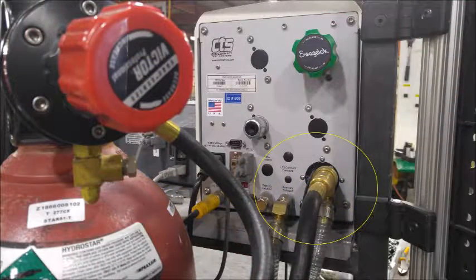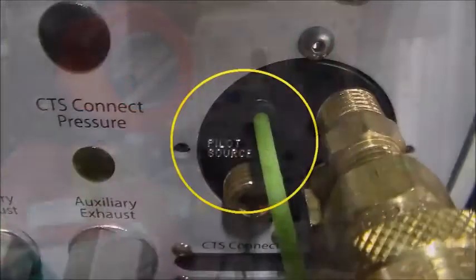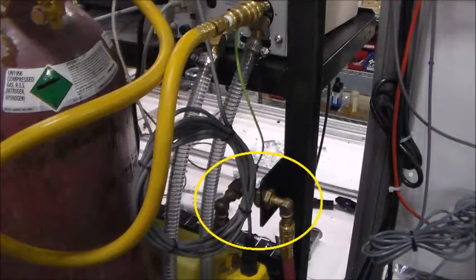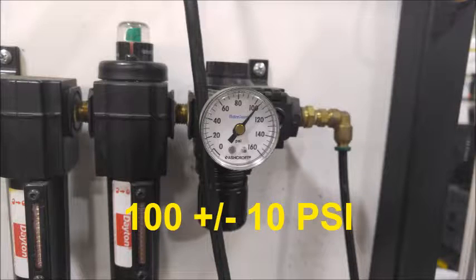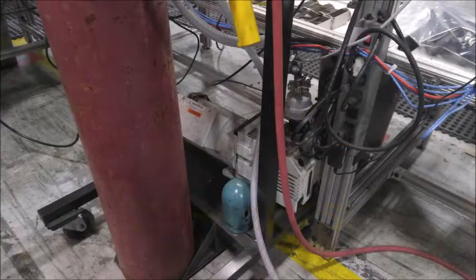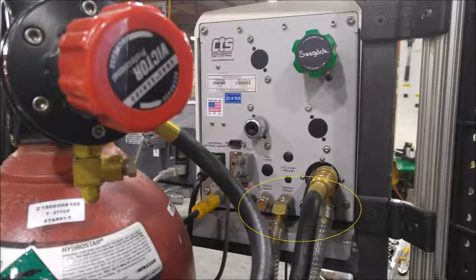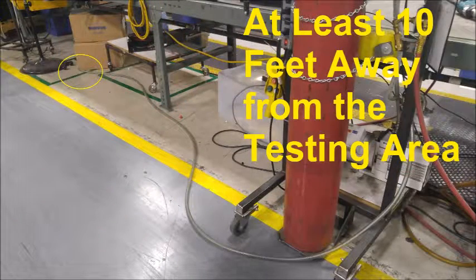For the TracerMate CS, make sure the hydrogen tracer gas hose is connected and turned on. Verify the pilot air hose is connected to shop nitrogen and set to 100 plus or minus 10 psi. If any of these pressures are incorrect, notify your supervisor or lead and they will contact the proper personnel to fix the issue. The vacuum pump part of the system must have a line connecting it to the TracerMate. The pump must be turned on and running, and the exhaust line must be routed at least 10 feet away from the testing area. This is so the exhaust gas won't tamper with the test results.